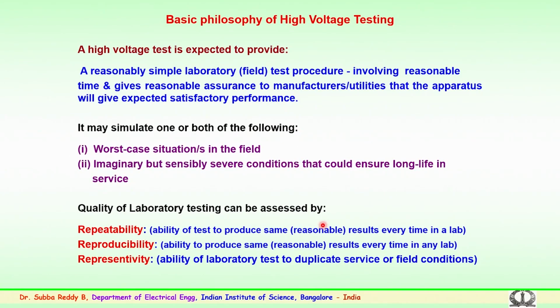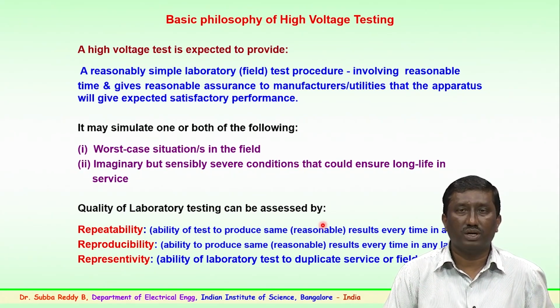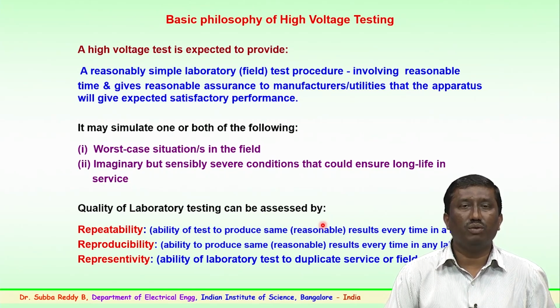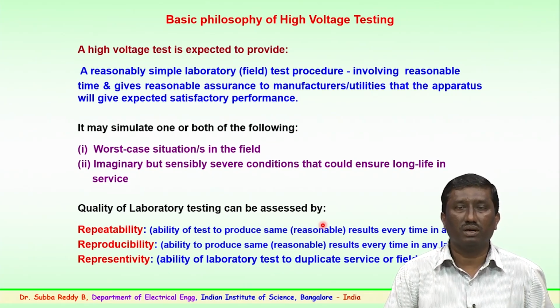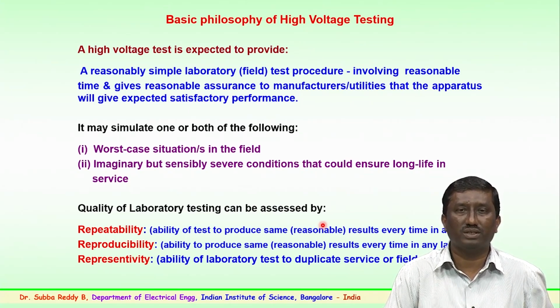So, when we look at the testing aspects, what is the basic philosophy which pertains to high voltage testing? Why is the testing essential for high voltage equipment? A high voltage test or verification being done in the laboratories or at the industry is expected to provide a reasonable field procedure. That is, when they are conducting tests or experiments on a particular product in the laboratory, it has to reasonably simulate the field conditions, and it should involve a reasonable time. In the sense, you cannot try to simulate in the lab for a large number of years or a long period of time.